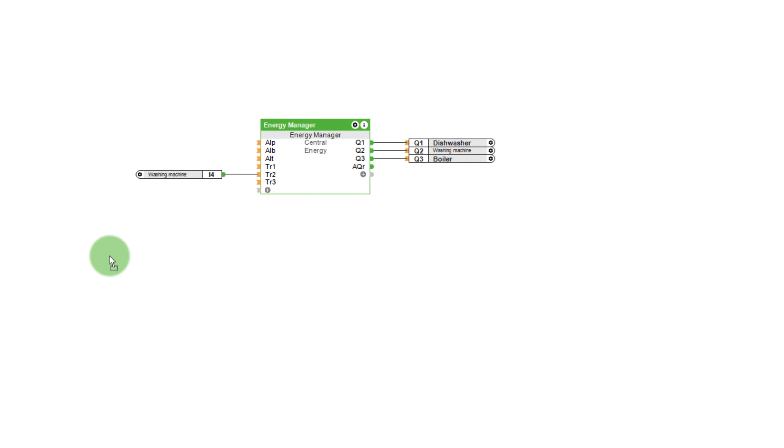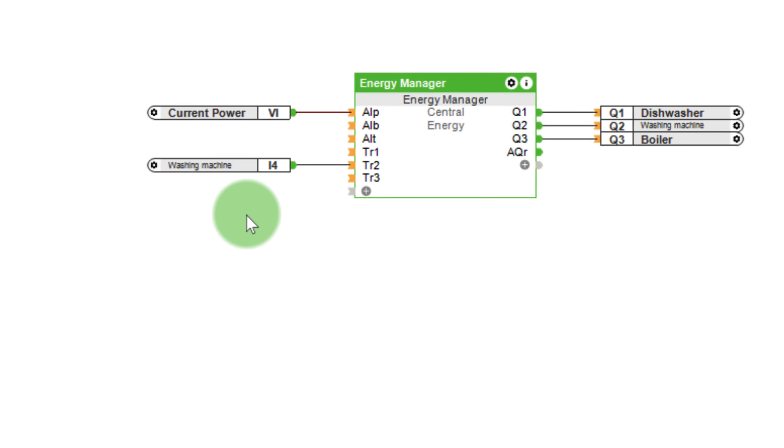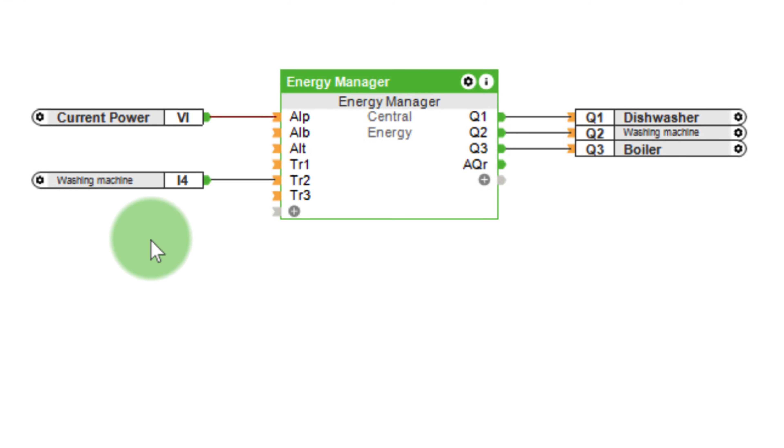In order for the energy manager to be able to perform its work at all, it has to know how much energy is currently being produced or consumed. Therefore, the current power is added to the input AIP. The value is positive if more power is being consumed from the grid and negative if more power is being self-produced than what is needed.